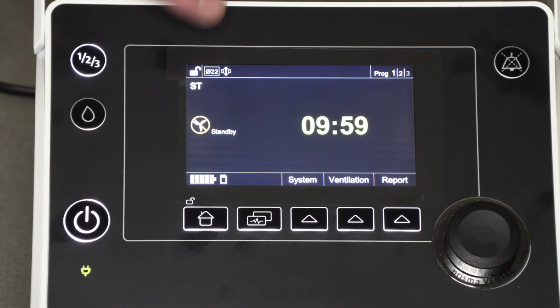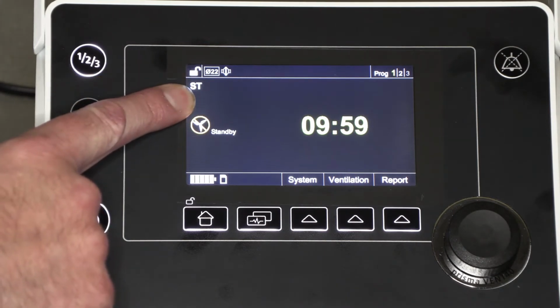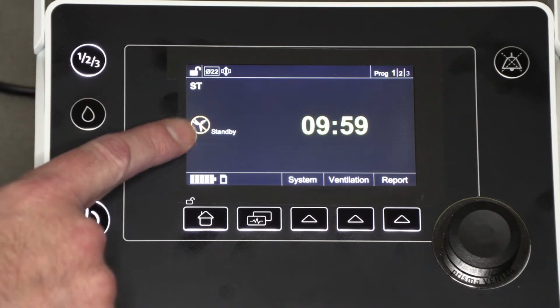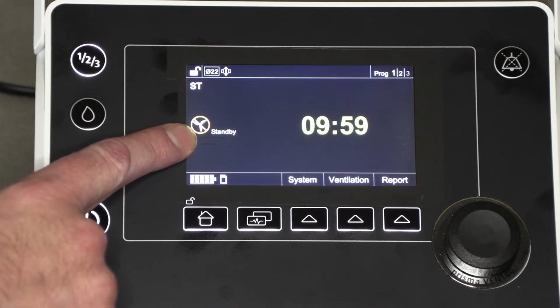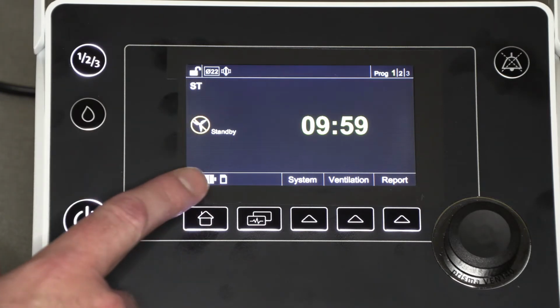Beside the lock symbol is a small rectangle with the number 22 inside. This means that this prismaVENT 40 is configured to be used with the 22mm breathing tube. The bacteria filter symbol means that this device is set to allow for the resistance of an applied bacteria filter. Moving down the screen, you'll see the current therapy mode set on the ventilator. Below this, you'll see the blower symbol with an X through it. This means the blower is currently in standby and is ready to be used. You'll also see the current time displayed in large bold digits.